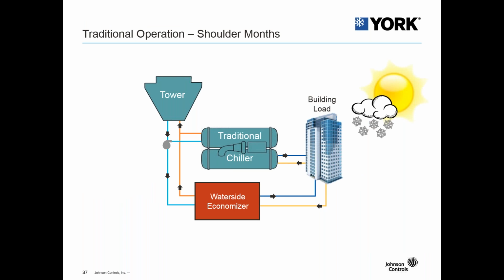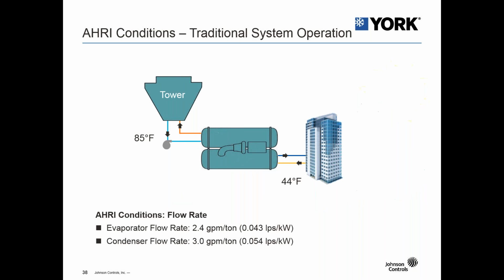But with having a water side economizer and a traditional chiller, there's always the shoulder months. So which one should be used in these scenarios? It's not really cold enough to use the water side economizer. Getting that tower water can't get you all the cooling you need in the shoulder months, and the tower water is too cold for the traditional chiller to run. It's below 65 degrees, but it's not low enough to provide 44 degrees to the system. So which one is used in the facility? And there's a lot of changeover problems between going from one system to the other.